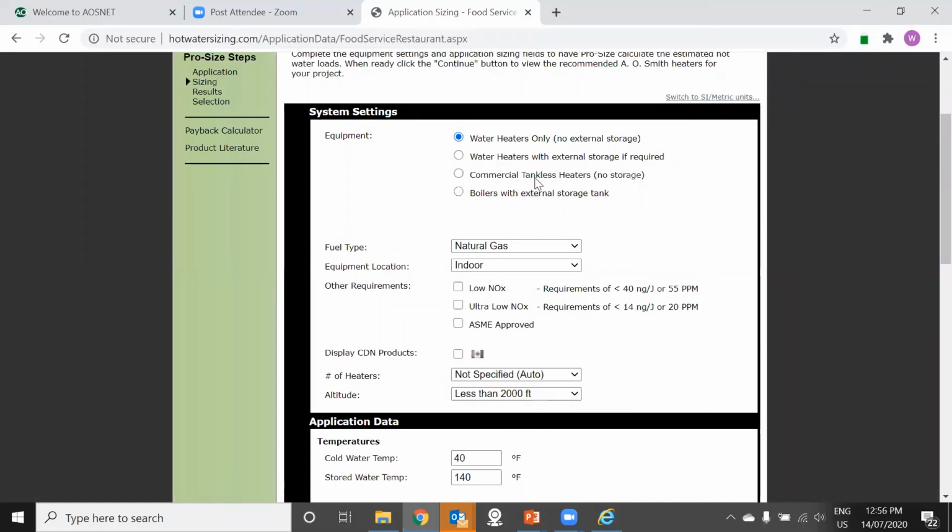We do tankless. Myself, in a commercial restaurant, I'm a little concerned about the number of cycles that could happen on a tankless heater. If you do the ASHRAE Hunter's curve, you'll notice that tankless water heaters all start at 4 tankless heaters for a restaurant.